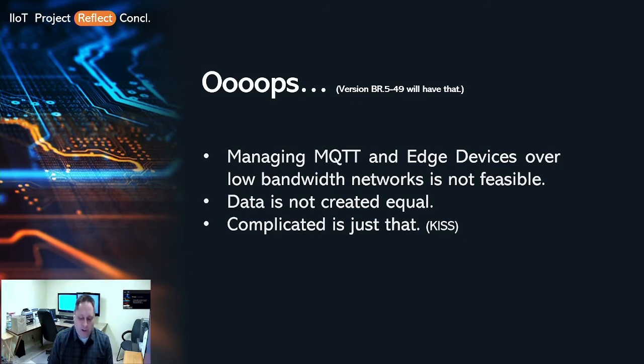All of the data is unrelated. They all get timestamps that are different, several seconds, even minutes apart from the other changes. And we found no way for us to re-relate that data into a record, into a data set, after it arrives through MQTT. So we had to abandon that portion of our development and just go back to using D-logs from our SCADA packs and ACM to pull that data. And it does handle it now as a record going through that mechanism.